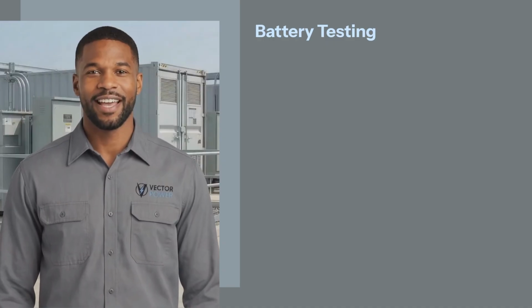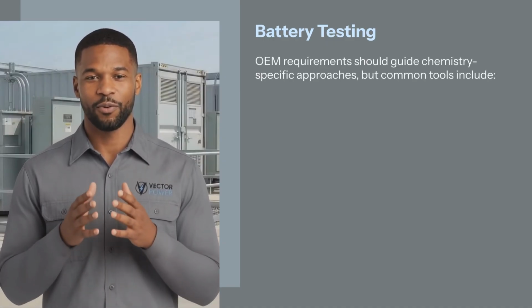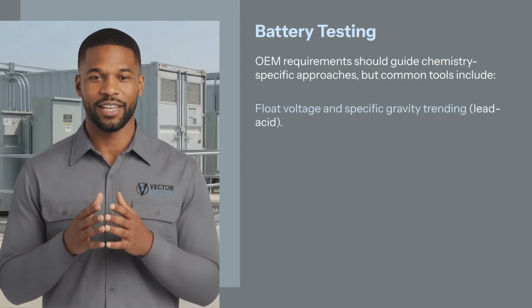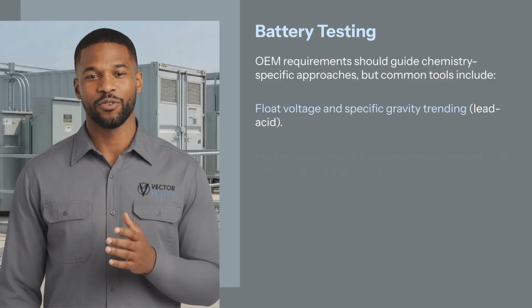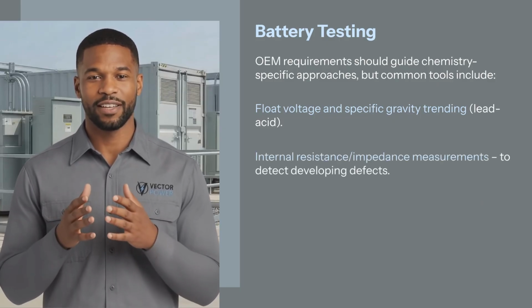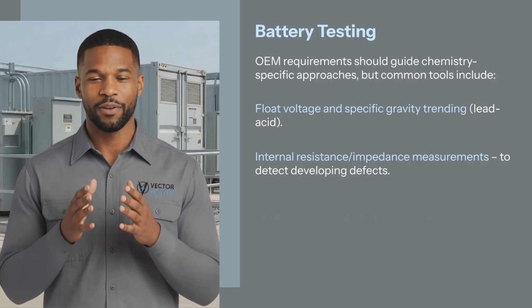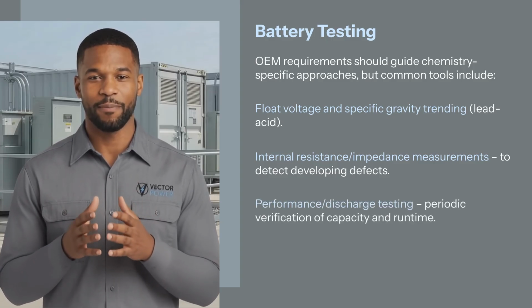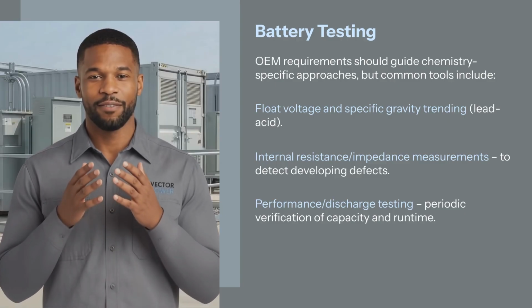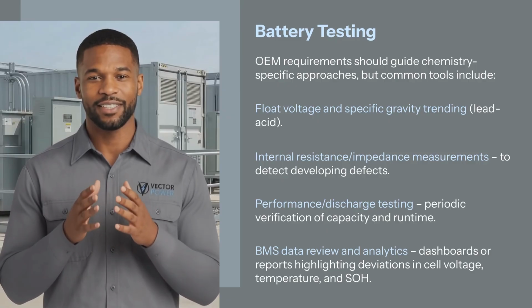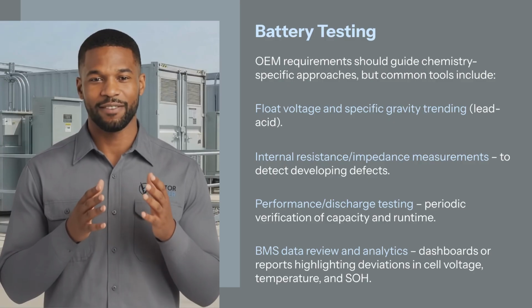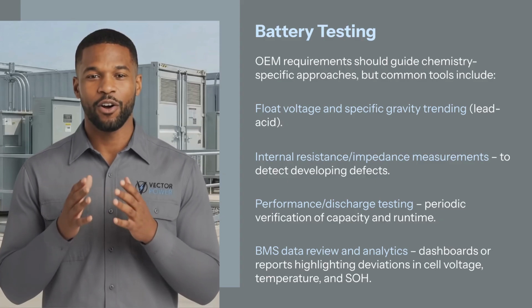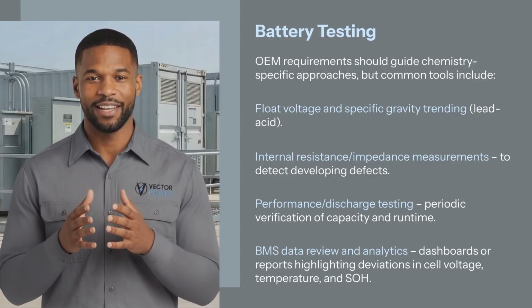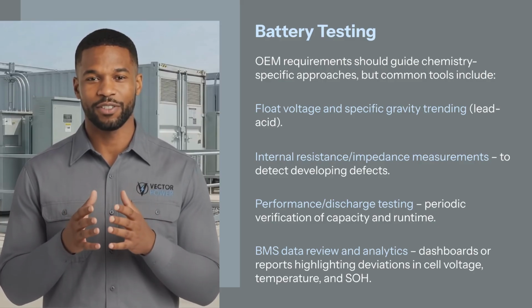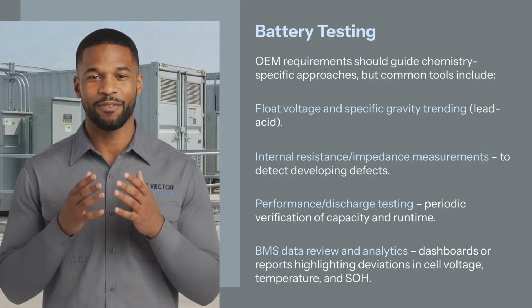Now let's take a top-level look at battery testing. Original equipment manufacturer (OEM) requirements should guide chemistry-specific approaches, but common tools include float voltage and specific gravity trending, particularly for lead-acid batteries. Internal resistance or impedance measurements, performed to detect developing defects in battery cells. Performance or discharge testing, performing periodic verification of capacity and battery runtime. And battery management system data review and analytics: review of dashboards or reports highlighting deviations in cell voltage, temperature, and state of health. All testing must be risk assessed in accordance with NFPA 70E and, where possible, performed without exposing workers to energized parts, for example, by using permanent test points, built-in diagnostics, and remote data access.